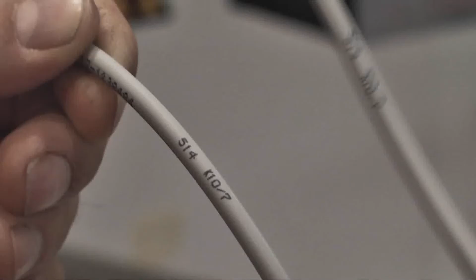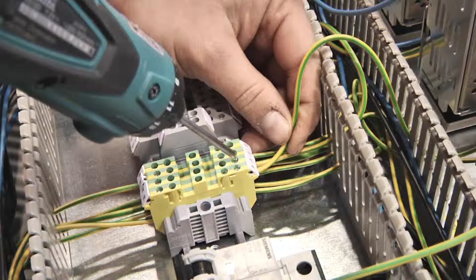When the electrical circuits on the base plate have been connected, we install them into the cabinet and then connect circuits to the cabinet casing for components such as fans, buttons, control panels or connectors. Finally, we connect all the non-live parts using a protective earthing conductor.